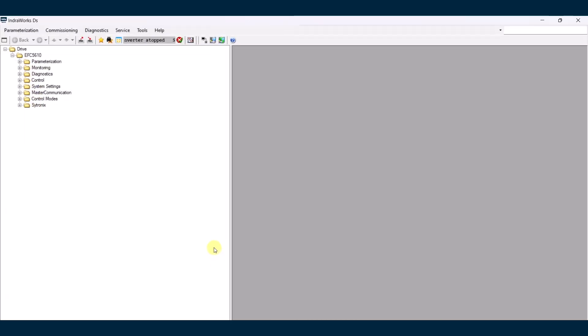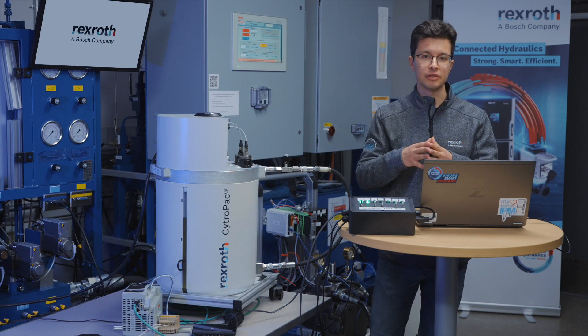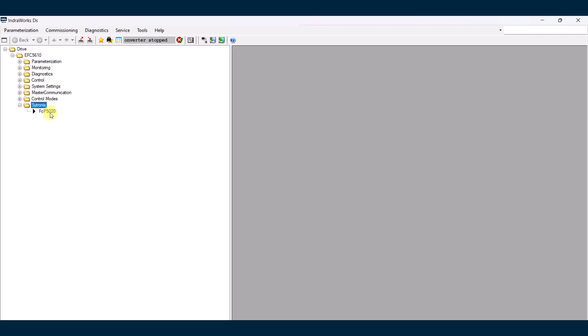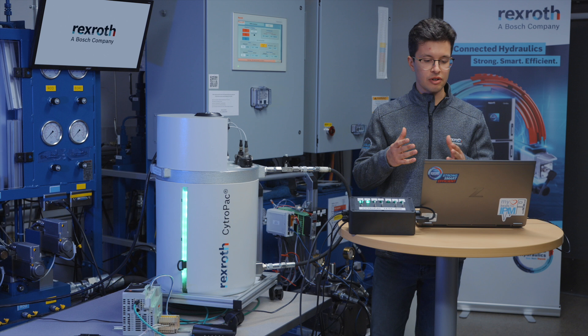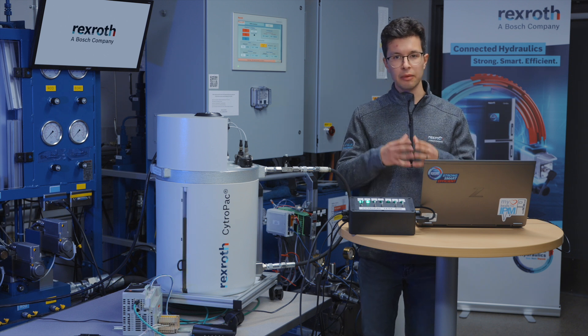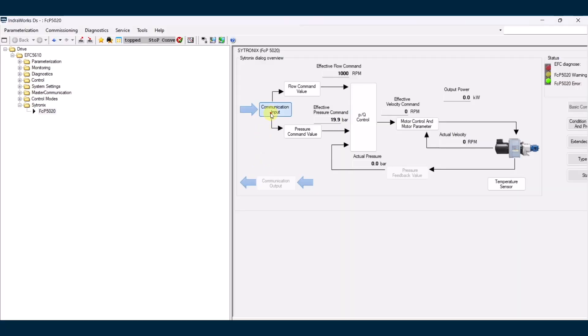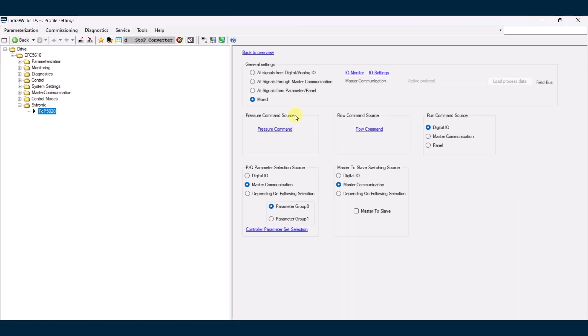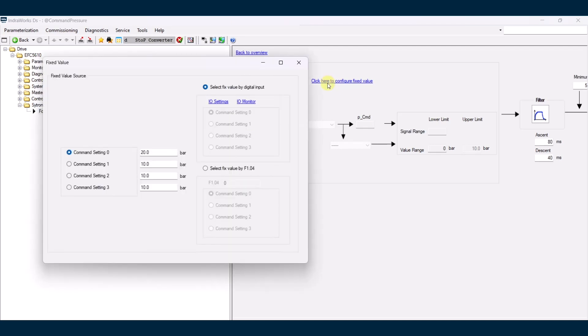Once you click connect, you'll be given the IndraWorks DS screens. There are many different screens, but the only one we're going to focus on today is Sytronix. We're going to select FCP 5020. For this demonstration, we're just going to enable the CitroPak to go to a fixed pressure and fixed flow. We'll start by clicking communication input on the left, then go into pressure command source. We want this set to a fixed value — in this case, 20 bar.